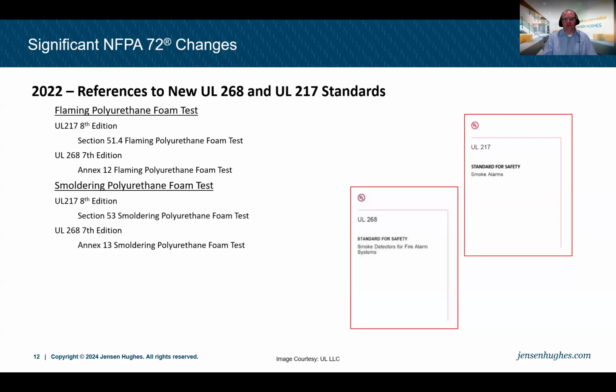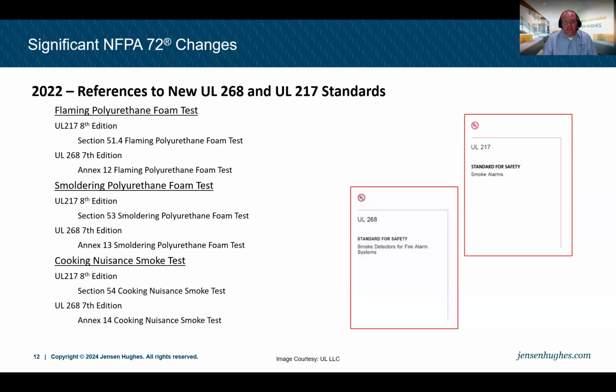Now, we use polyurethane everywhere in our construction materials. It's in our chairs, our couches, our carpets. Basically, all of our building materials have some kind of polyurethane foam or polyurethane component to it. So we wanted to make sure we were providing smoke detection that would alarm when exposed to this kind of smoke, either flaming or smoldering. And then the third test was a cooking nuisance test, added because we don't want our smoke alarms or our smoke detectors to be overly sensitive to nuisance materials, particularly cooking nuisance material.